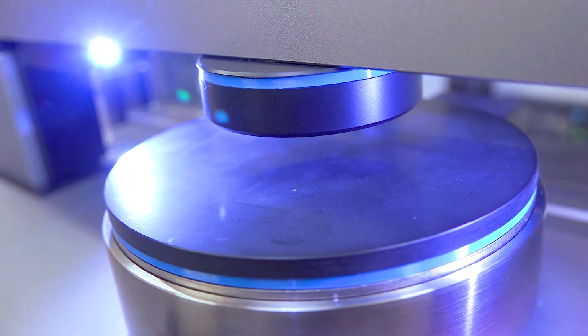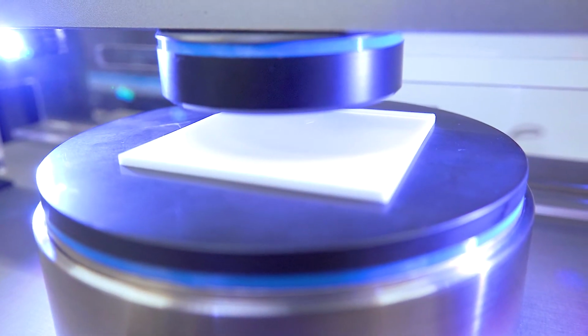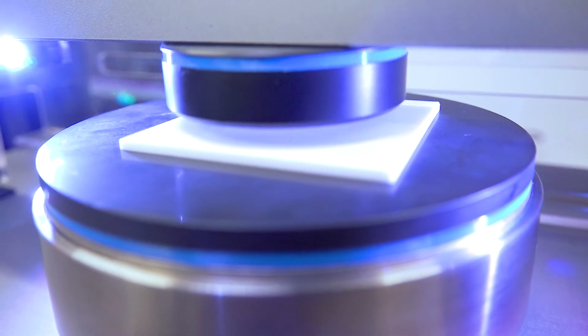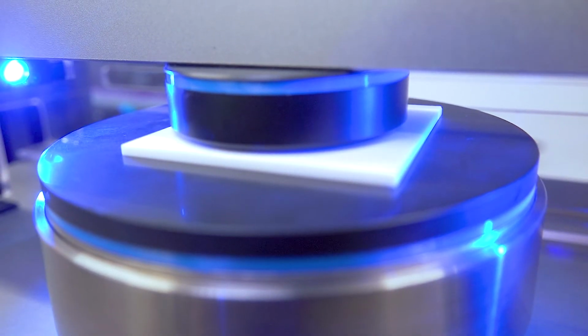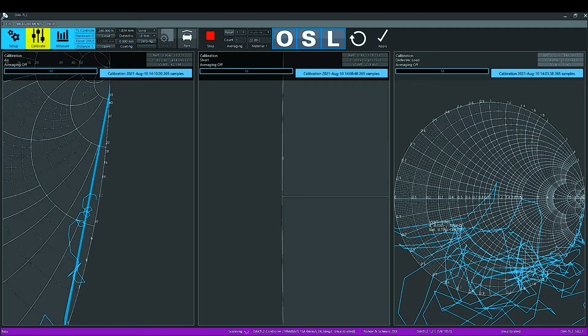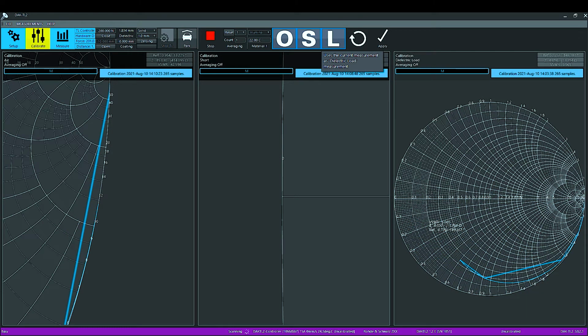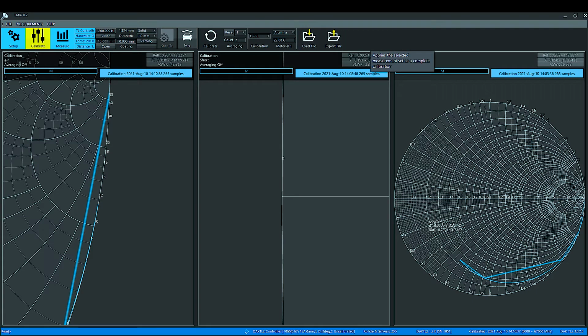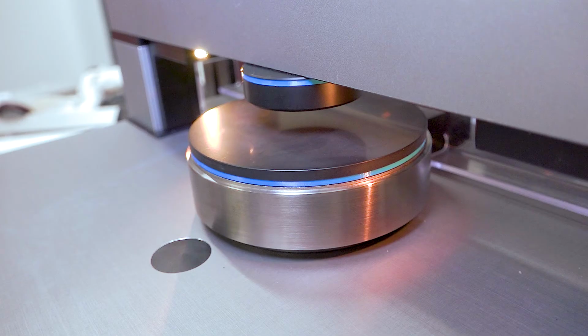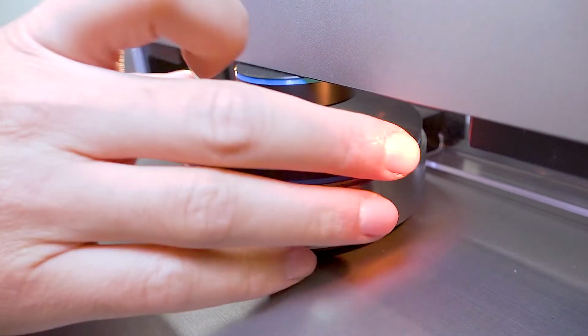Step 8. I place the load on the lossy platform and close it with similar force used during zeroing. When the trace on the Smith chart is stabilized, the load calibration button is pressed. As the last step to complete the process, I press the Apply button to store the calibration. Open and short calibration for liquid measurement is similar to what we just did for solids. I only need to use a liquid as the load.